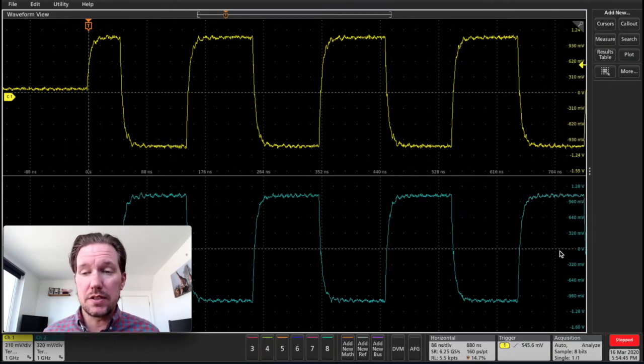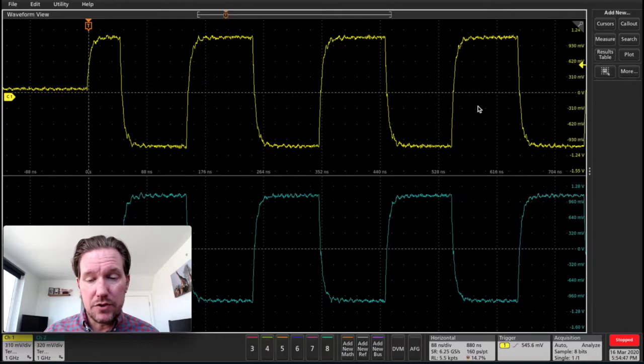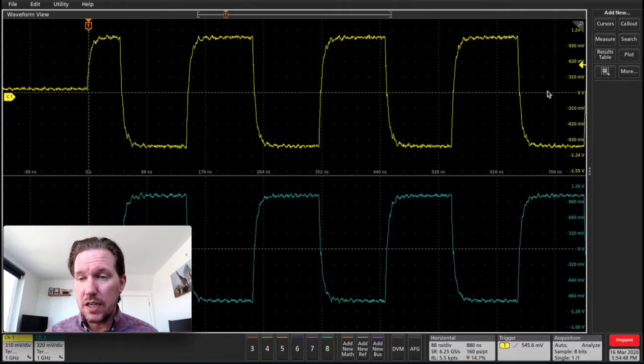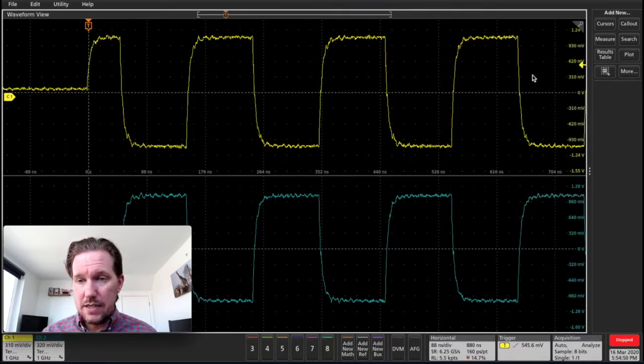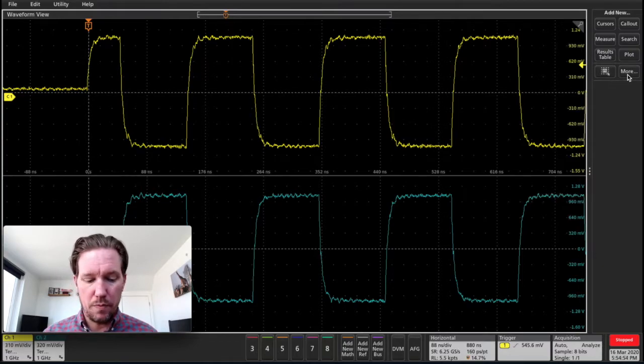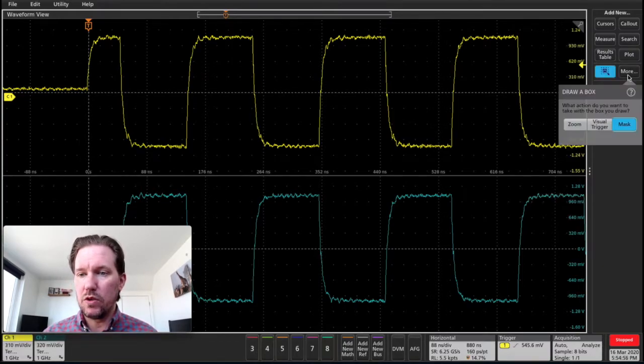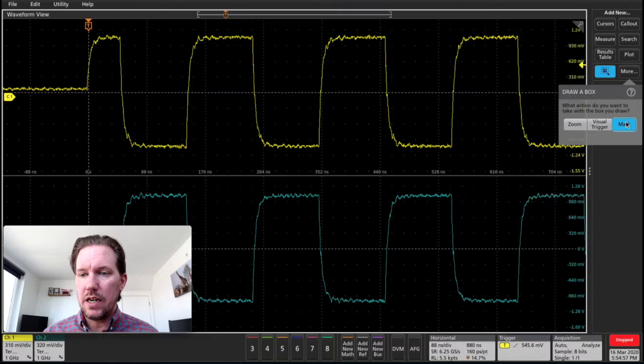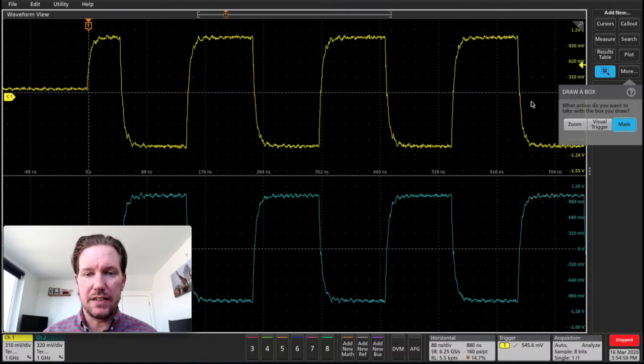So to do this, let's just jump right into it. I have two waveforms on the screen here, and to get my mask test going, I'll go over to the right to this More menu and tap on that once, and we'll see mask is highlighted here.